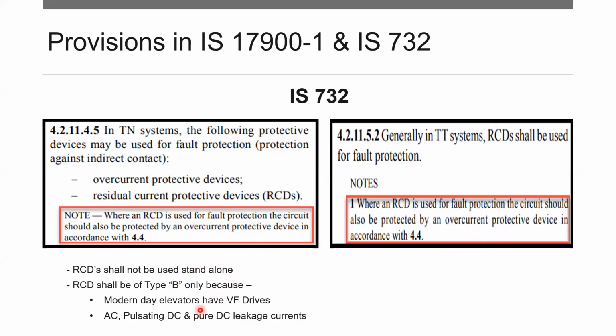And since modern day elevators have VF drives, which have AC, pulsating DC, as well as pure DC leakage currents, the type B RCD is mandatory. We cannot go with type A or type AC, which is a common mistake happening today in the elevator industry, where people are also using other types of RCDs, which is a violation.